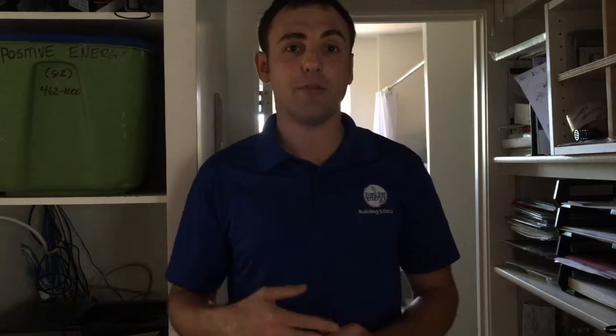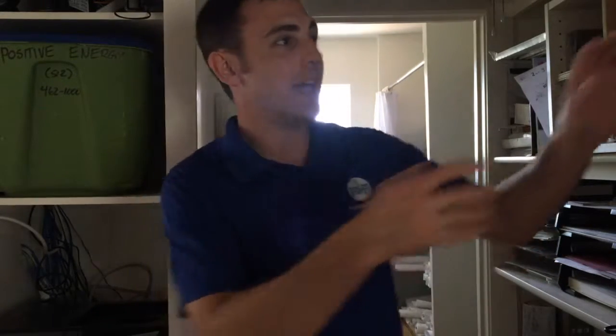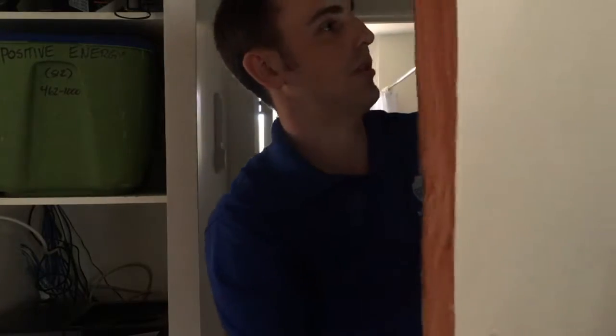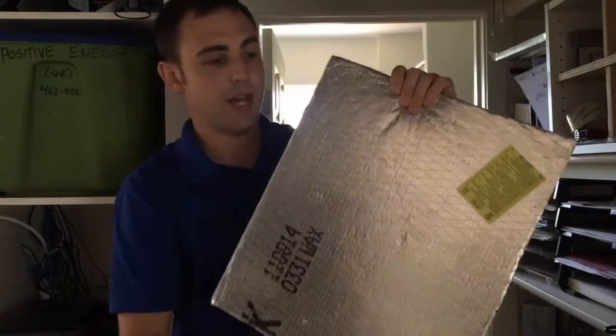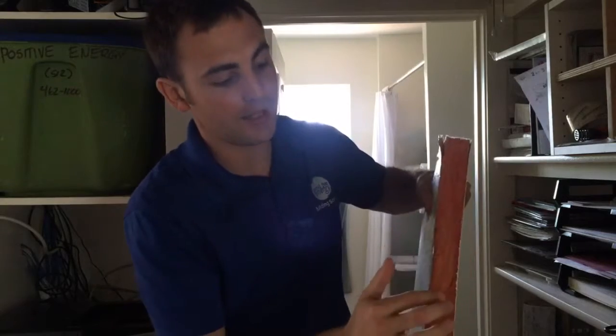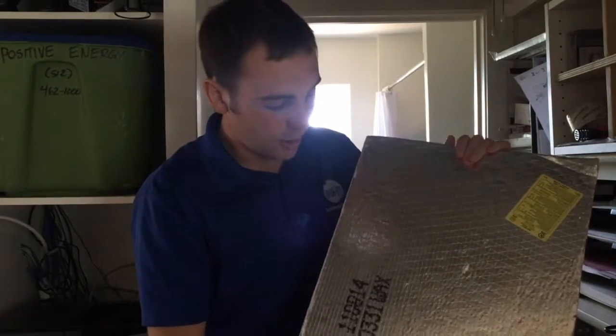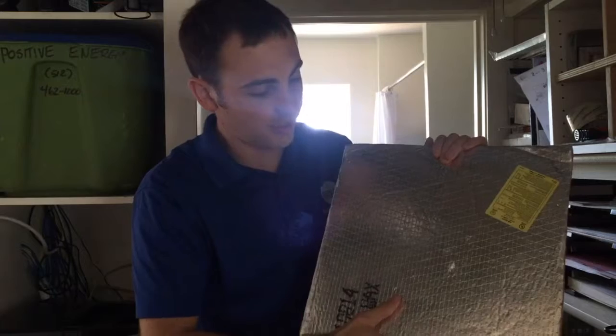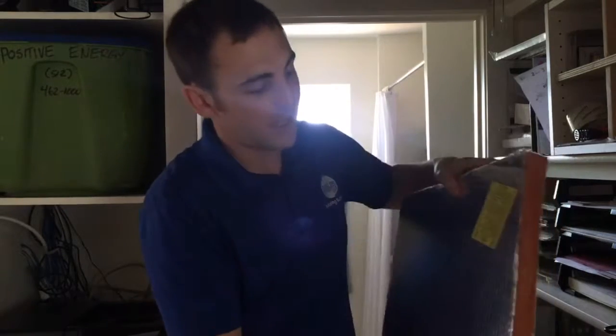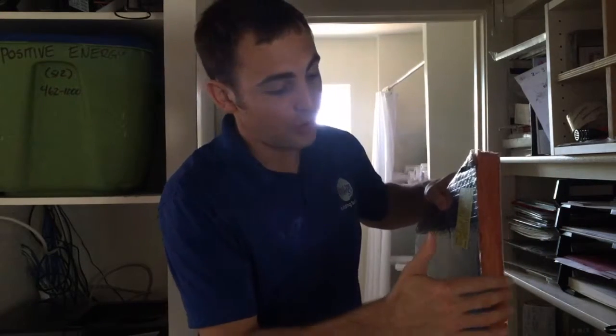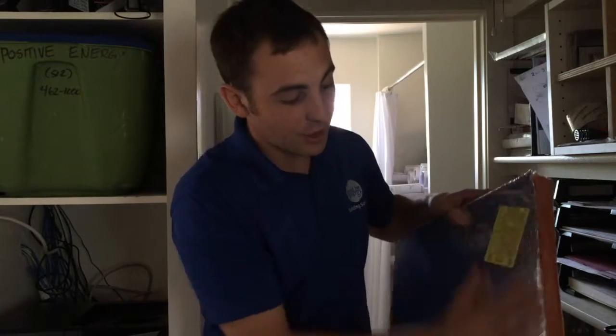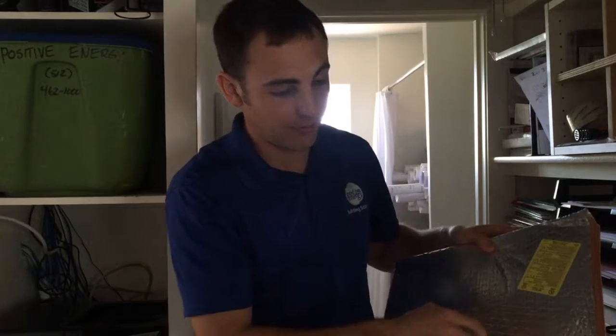The third main type of ductwork is ductboard, and typically ductboard is used in conjunction with your flex duct, and that sort of looks like this. This is going to be the outside, and then this is the inside insulation. So ductboard here, you can see it's got this reflective liner. This is its air liner. Inside here is the insulation. And if you don't have an air barrier on the inside, you really need to make sure that this air liner gets sealed, because any sort of penetration or cut in this is going to cause lots of duct leakage.